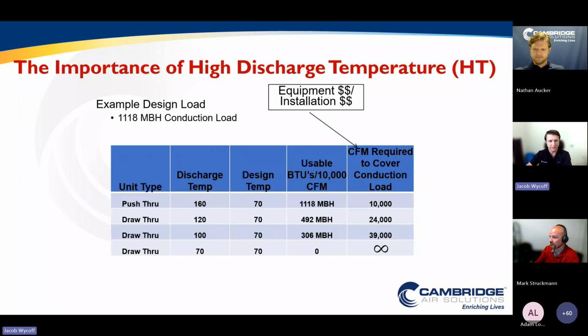I think we see where this is going. Whenever you restrict the discharge temperature and have much more CFM, it's going to have larger equipment that's more costly to install. But more importantly, you're going to be wasting energy as you are having a much larger fan that needs to run. And more importantly, you're wasting fuel treating a large amount of outside air that's way above any ASHRAE 62.1 minimum ventilation requirement you might see in a warehousing or distribution type space, which is going to be much more costly for the user and a much less efficient way to heat that space.